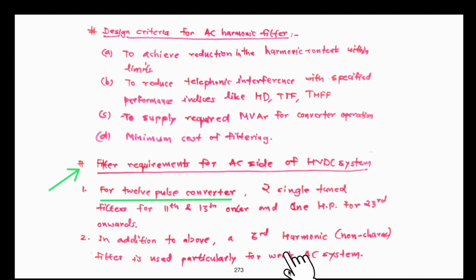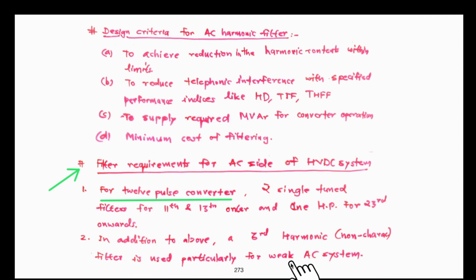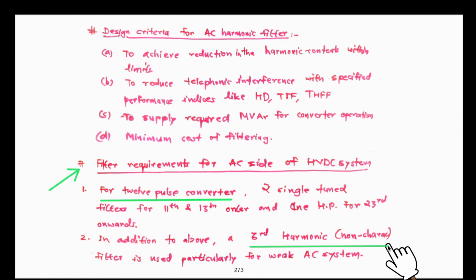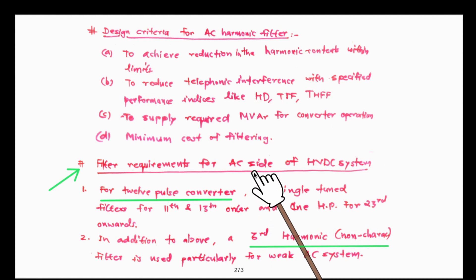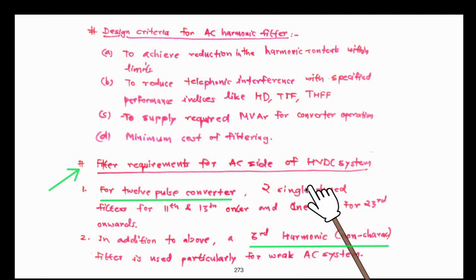In addition to the above, a third harmonic non-characteristic filter is used particularly if the AC system connected to the HVDC converter is a weakly connected or non-meshed network. Third harmonics are not present in all systems, but in a weakly connected network there may be disturbances in AC voltage — unbalanced voltages — and in such cases a non-characteristic harmonic filter must be in place. So for the AC side we have two single-tuned filters, one high-pass filter, and one non-characteristic filter — four filters in total.